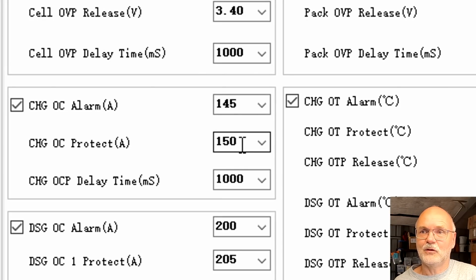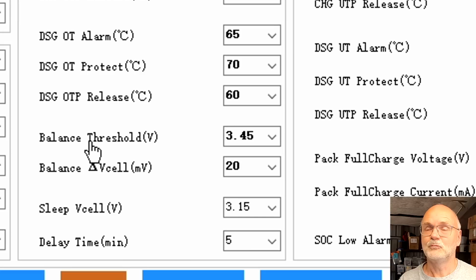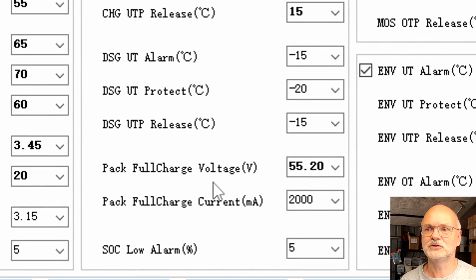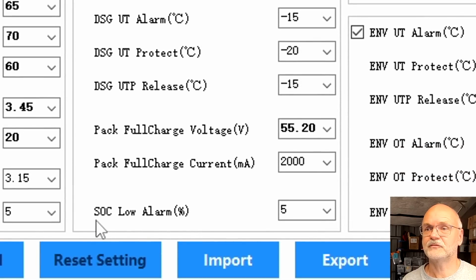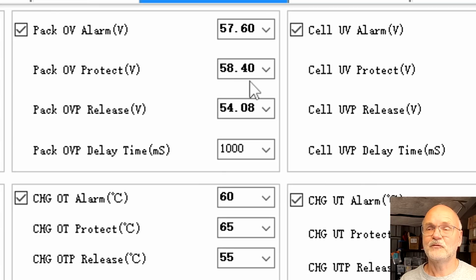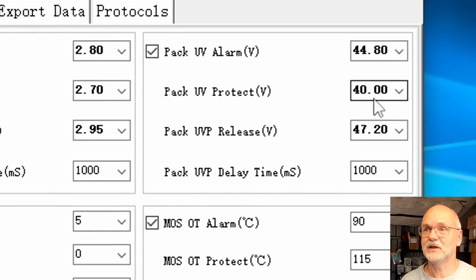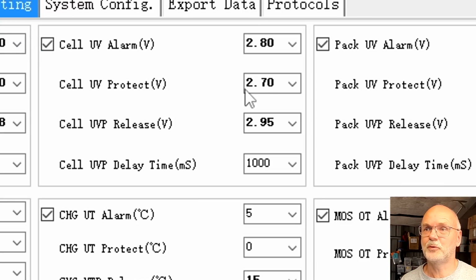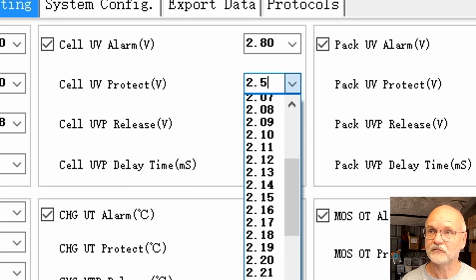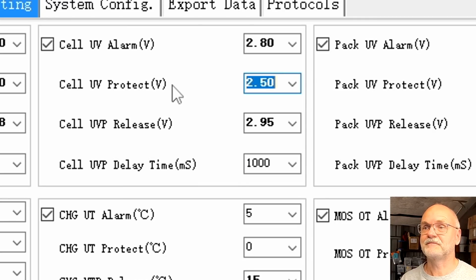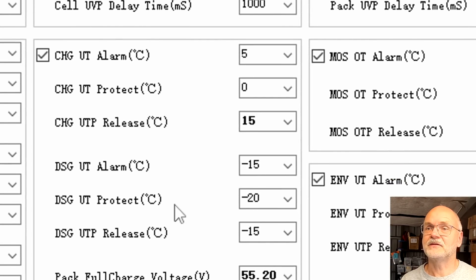145 alarm, 150 over current protection for charging, and 200 amps discharging. We've got a balance start voltage of 3.45 volts, balance deviation of 20 millivolt, and a pack full charge voltage of 55.2 volts. 2 amp is our tail current and the low state of charge alarm sits on 5%. 58.4 volt pack voltage, 40 volt pack voltage on the lower end. Cell under voltage protection 2.7 volts. Well, we have to change this one to 2.5, don't we, because we want to do a full discharge test. Charge under temperature protection at 0 and discharge under temperature protection at -20.